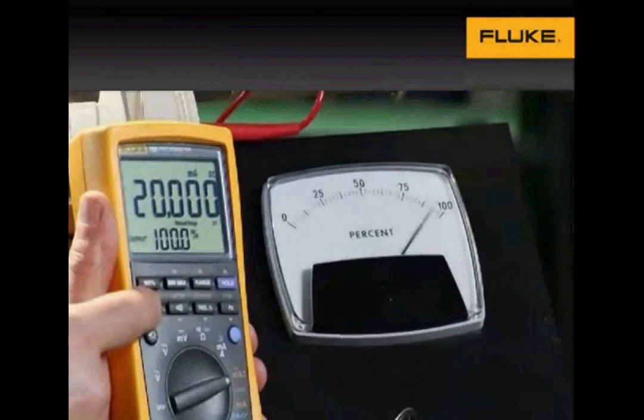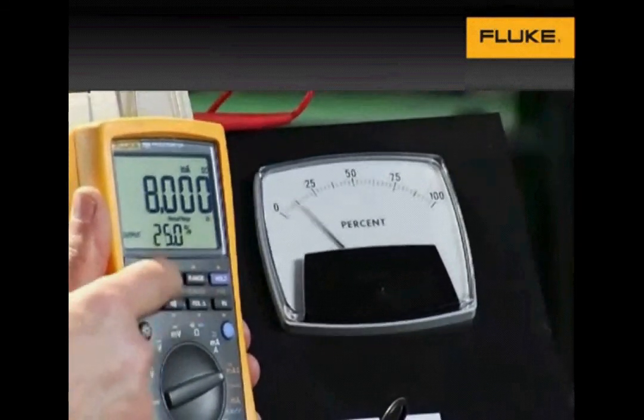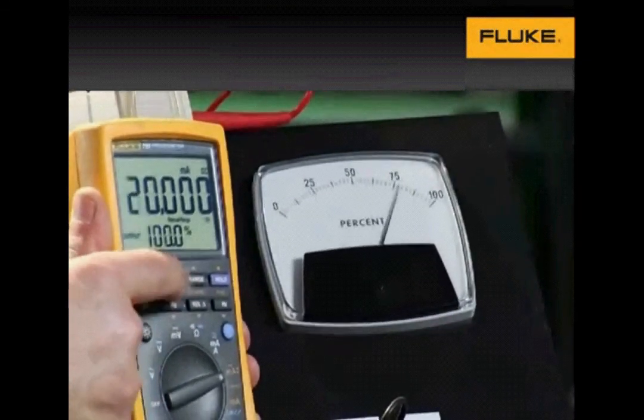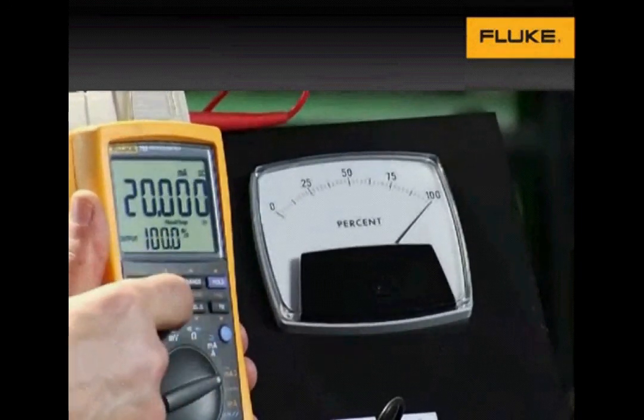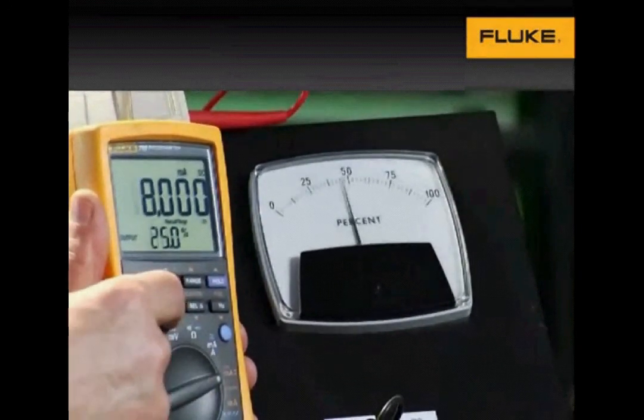You can go from zero to span and change the output in 25% steps, change the output in one-tenth of a milliamp steps, or one microamp steps for fine tuning.